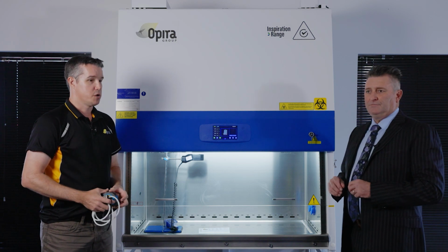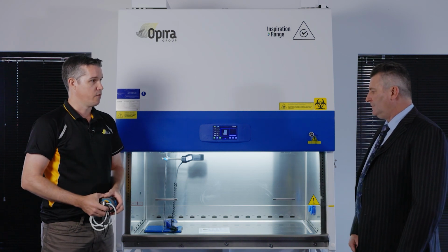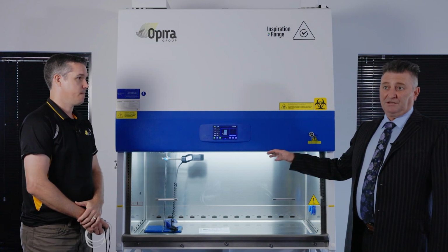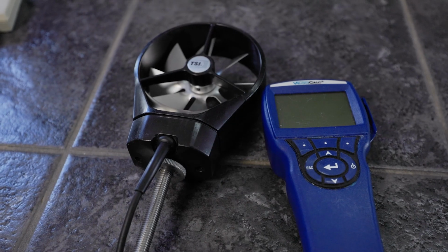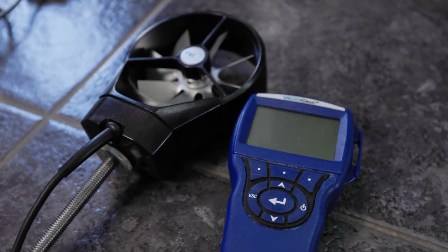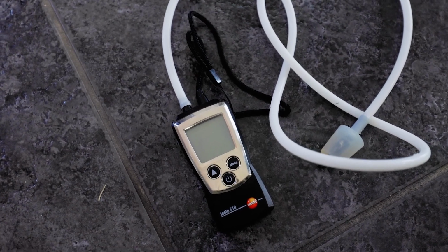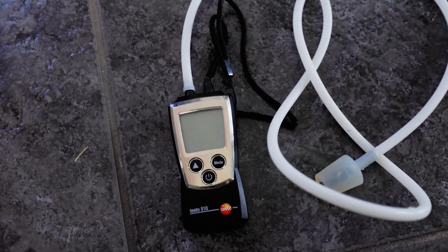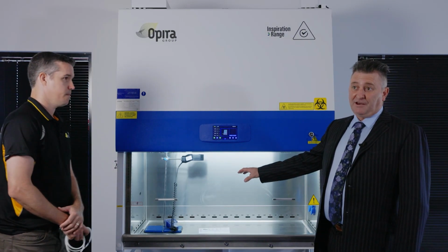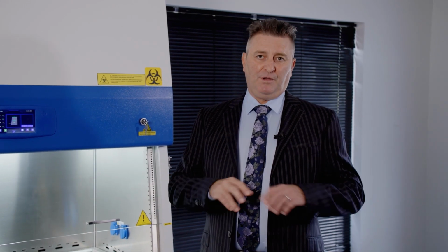That's right. Apply the correction factors that'll come with the calibration report for the anemometer. So it's important that the technicians are using calibrated equipment, and that equipment also needs to be calibrated at another calibrated lab. So don't feel scared about walking up to your technicians and just checking that their gear's calibrated. Yeah. Because that's the accuracy that we're dealing with, because we're putting a correction factor into some software when we're doing the report to give you a number which is important for a pass-fail.